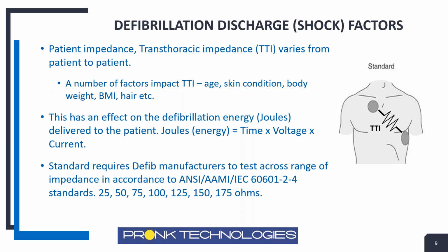Manufacturers of defibrillators have an international standard they have to test to when they're designing their devices, and they submit their information to the FDA saying, look, we've done this testing, we've confirmed that the defibrillator will discharge within its specified tolerances across various common impedances of a patient. The standard calls for manufacturers to test from low impedances of 25 ohms all the way up to 175 ohms. The manufacturer has to do this to make sure the defib can discharge within tolerance under all those various conditions.